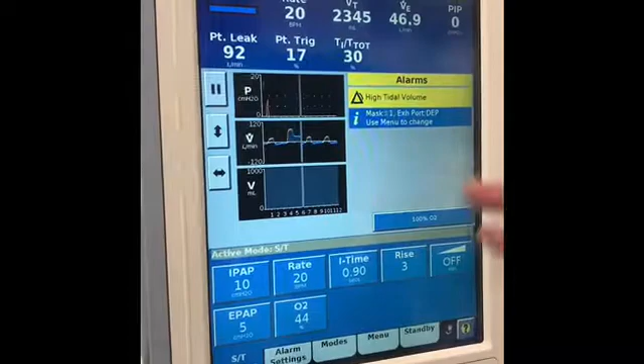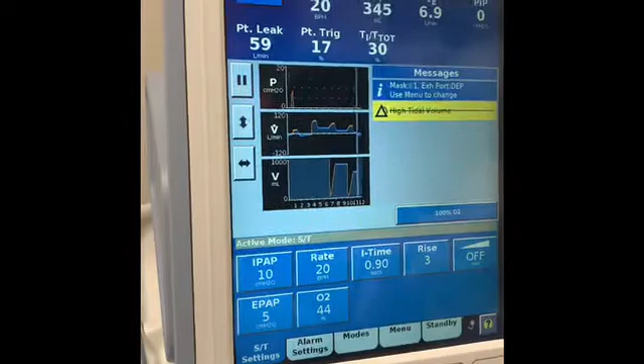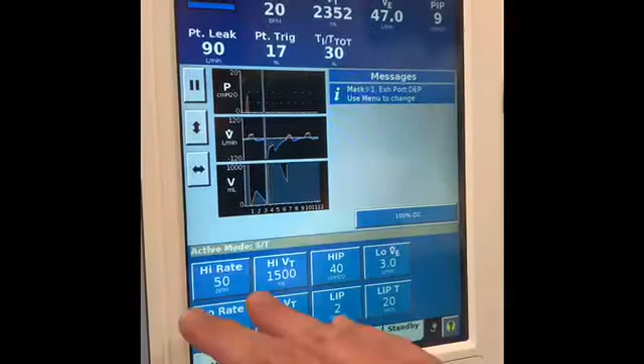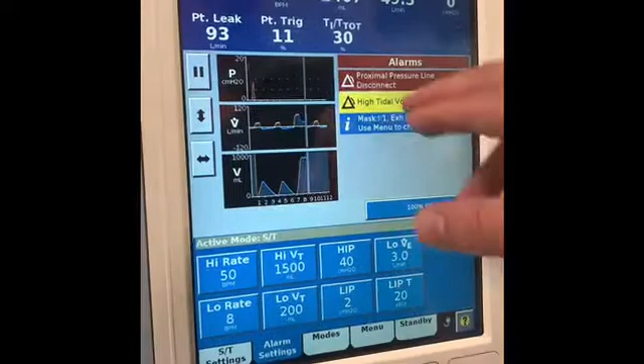Your I time is usually 0.9. The rise means how fast the air goes up into the patient. We usually set that at about 3. There is a backup rate, even though this machine is spontaneous and timed. So we keep that around 20. It's alarming because there's no patient on it. So that's why it keeps alarming. So there's alarm settings as the next button. You've got your high rate, you've got your low rate, which are probably the most important ones. And yeah, those are definitely the two most important ones.